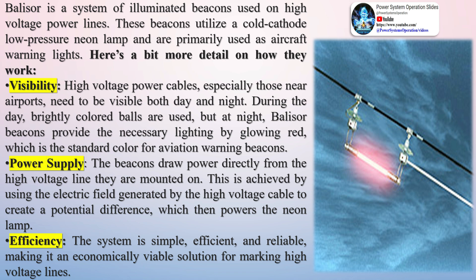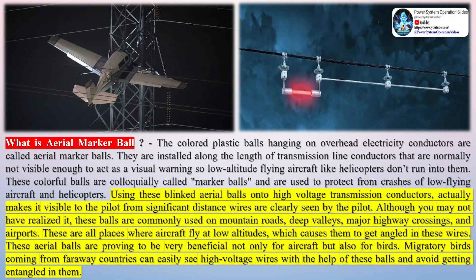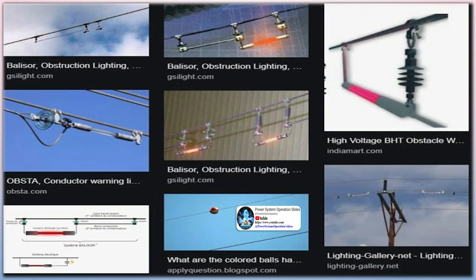Here's a bit more detail on how they work. Regarding visibility, high-voltage power cables, especially those near airports, need to be visible both day and night. During the day, brightly colored balls are used, but at night, Balisor beacons provide the necessary lighting by glowing red, which is the standard color for aviation warning beacons. The beacons draw power directly from the high-voltage line they are mounted on, using the electric field generated by the cable to create a potential difference which then powers the neon lamp. The system is simple, efficient, and reliable, making it an economically viable solution for marking high-voltage lines.